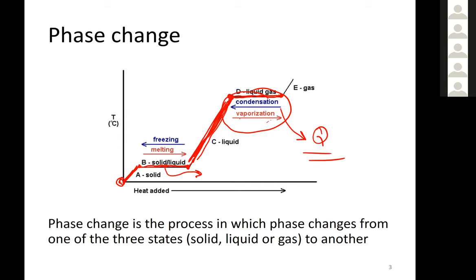So our cooling process, when we talk about an air conditioner, is going to have a cycle, and that cycle is going to switch between condensation and vaporization of the freon or the working fluid. At that phase change, heat will be transferred between my medium of interest. For instance, in cooling, my medium of interest is going to be my room and the outside, which in that case is the outside atmosphere. So these two heat transfer processes are going to take place at almost constant pressure and constant temperature for the freon. And that's why we like to have phase change.